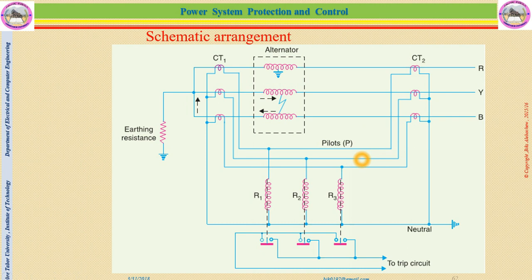Those two groups, CT1 and CT2, are connected by some wire. This wire is called pilot wire or pilot cable, and the terminals of this pilot wire at the middle of the two CT groups are connected in a star way. They are connected in a star connection, as you can see here, and this star has one common wire, which is the fourth pilot wire, and this also connects to ground, or the neutral. This is the neutral wire for the two. So the secondary parts of the CTs are connected inside.